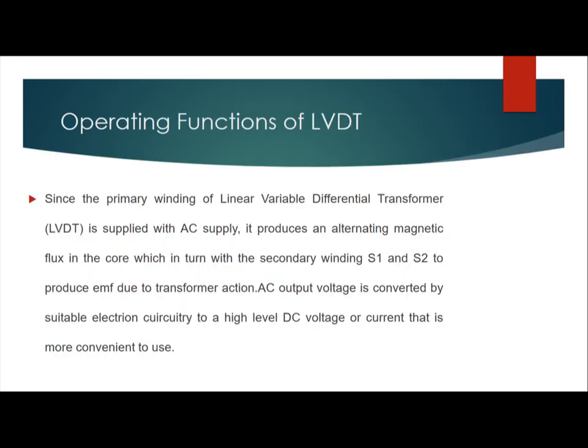In the operating functions of LVDT, since the primary winding of the linear variable differential transformer is supplied with AC supply — AC supply is for the transducer — it produces an alternating magnetic flux in the core, which links with the secondary windings S1 and S2 to produce EMF due to transformer action. The AC output voltage is converted by suitable electronic circuitry to a high-level DC voltage or current that is more convenient to use.